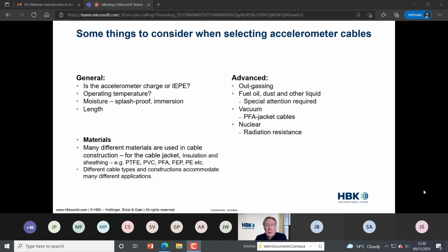Okay, there is no point whatsoever in choosing your accelerometer carefully for a particular task if you don't also give some consideration to the choice of cable. Some of the questions you need to ask about cables: is the accelerometer charge or IEPE? For charge output accelerometers, you need a higher class of cable, low noise or super low noise. Can the cable cope with the temperature range of the measurement? If it's a PVC cable, perhaps not. Is the cable waterproof? What about the length of the cable? Will that affect the measurement?